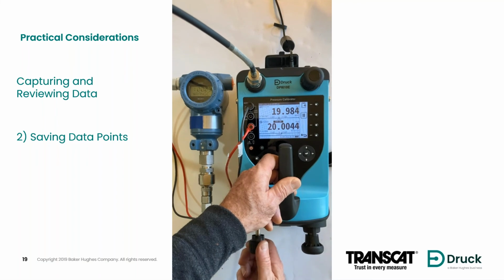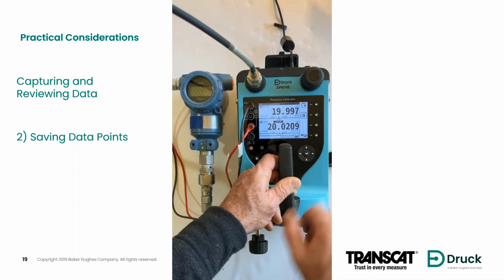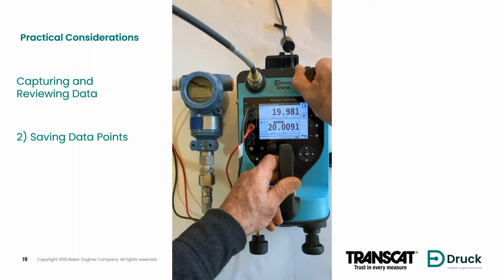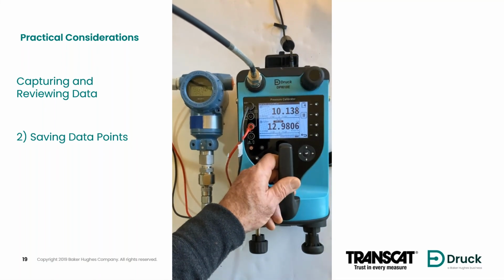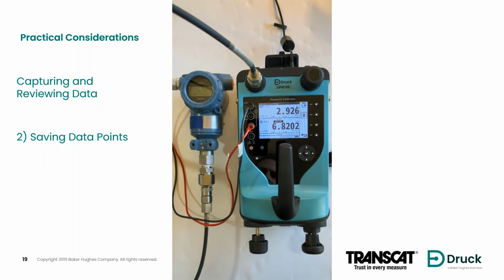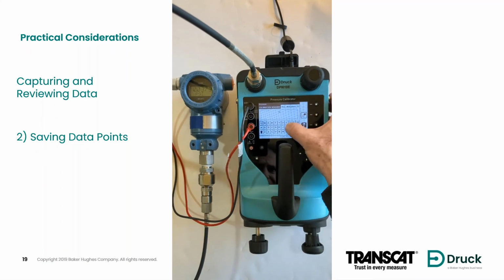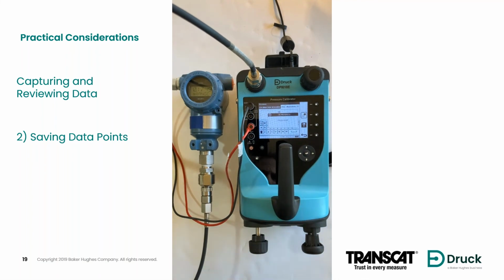Just in the interest of full disclosure, on the previous one where I had the pressure transmitter close coupled to the test port, you'll remember I got 25 psi per stroke of the pump. On this one, I'm not getting quite that much, but I do have significantly more volume on that hose that I've used to connect to the pressure transmitter. So not quite getting the same pressure amount per pressure stroke, but it's still pretty good given the volume that I got going there. So I captured a reading at 20 psi, and then I went back down to 0. It gives you the opportunity to enter comments at the end of the calibration, and then you save that data.